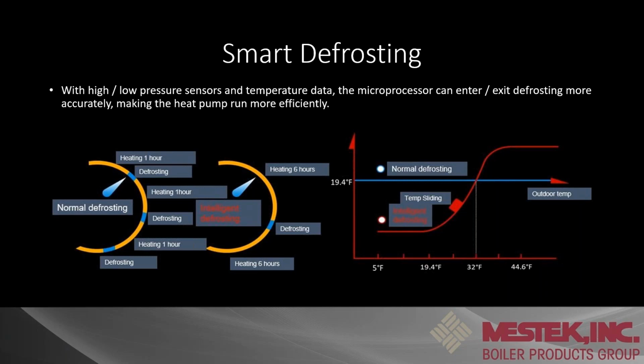Typically, you know, 40 degrees down to 0 degrees. As we get to 0, that moisture in the air is not as present, so you may not go into defrost as much. What I've seen out there in the past is defrost could happen on a timer. So basically, you're in heating mode, and every 60 minutes it goes into defrost. Well, that's no good, because if you go into defrost, you are now delivering cold water versus hot water. And we have to make that up, whether it is an electric backup or a gas-fired boiler, to keep that temperature going. So with our product and the way it's been designed now, we use pressure.